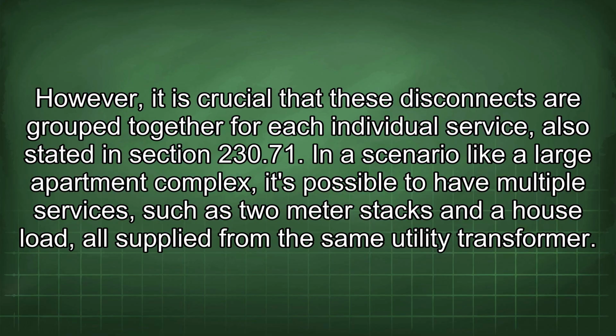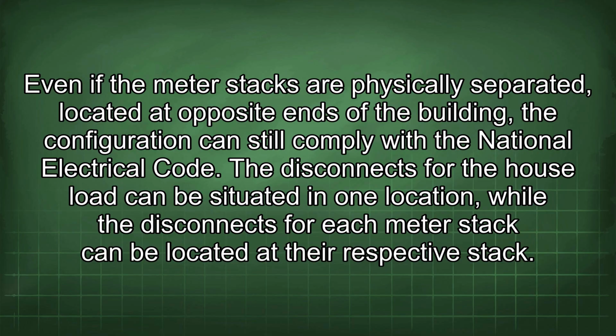In a scenario like a large apartment complex, it's possible to have multiple services, such as 2 meter stacks and a house load, all supplied from the same utility transformer. Even if the meter stacks are physically separated, located at opposite ends of the building, the configuration can still comply with the National Electrical Code.